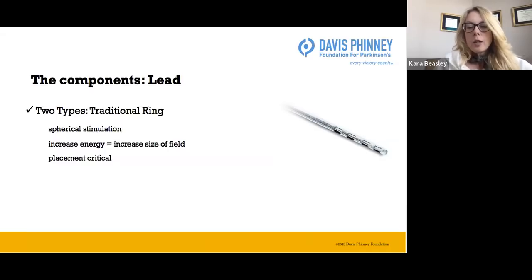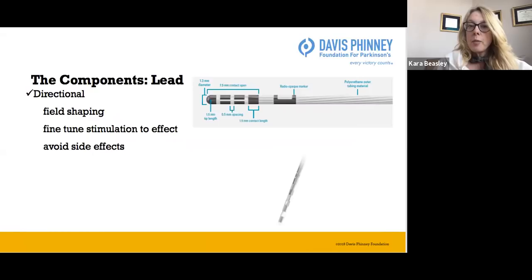Traditionally, for the last 20 plus years, there was only a traditional ring type lead. What that means is those little metal contacts that you can see on the picture here would provide stimulation in a circle around that lead. Increasing energy, or jacking up the voltage, would increase the size of the field. And in this situation, placement is very critical. These are deep, small structures in the brain, and so if you have to turn up the energy so much, you can get bleed over into other structures, causing side effects.